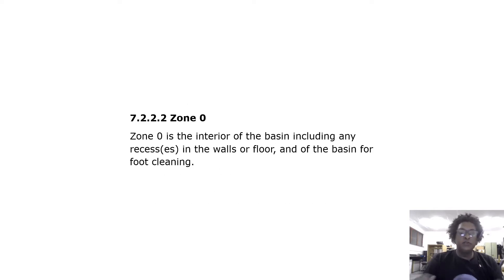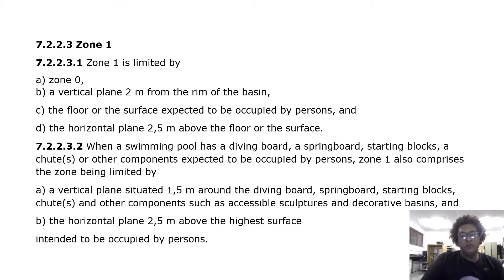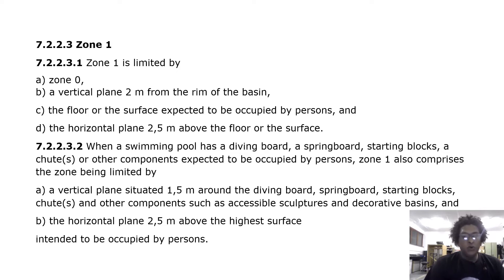Zone 0 is the interior of the basin, including any recess in the walls or floor of the basin, for foot cleaning. Zone 1 is limited by zone 0, a vertical plane 2 meters from the rim of the basin, the floor or surface expected to be occupied by persons, and the horizontal plane 2.5 meters above the floor or surface.